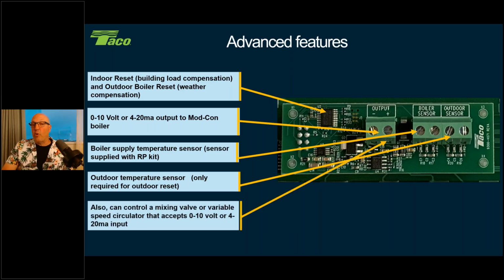Now, if you don't have a boiler that's accepting that 0 to 10 input, all right, we can also do some other things with that, like a mixing valve and control the water temperature separately, or a 2-temp system with a mixing valve that can accept a 0 to 10, or even, hey, a circulator that might have a 0 to 10 input. So that'd be really cool if a manufacturer made circulators that had a 0 to 10 input, huh? So.